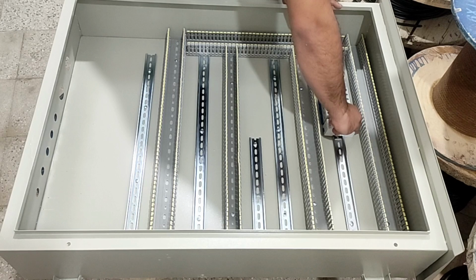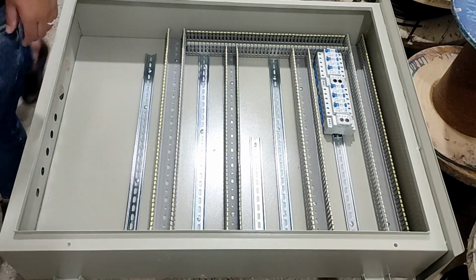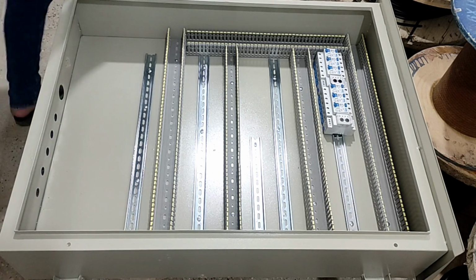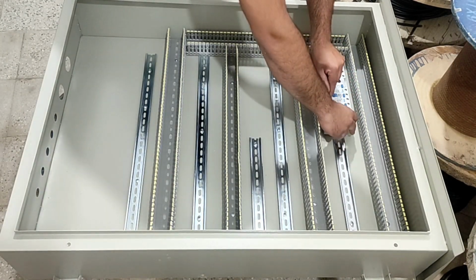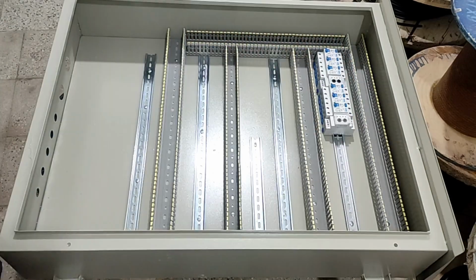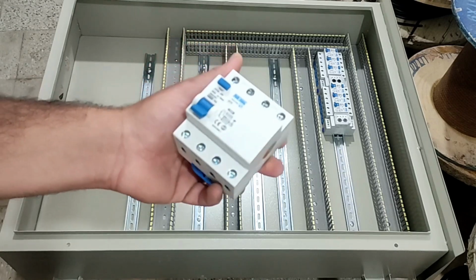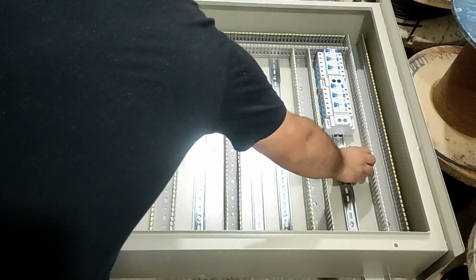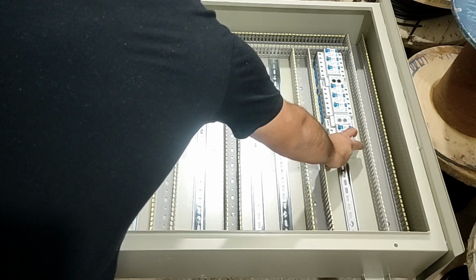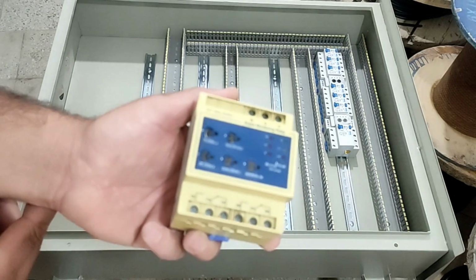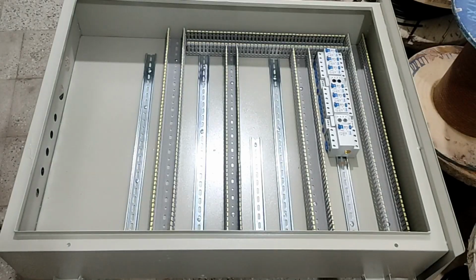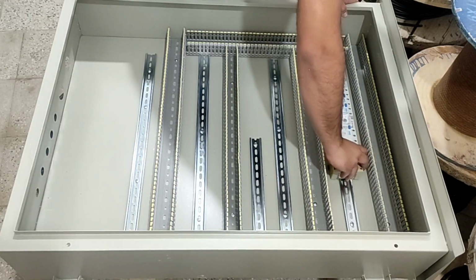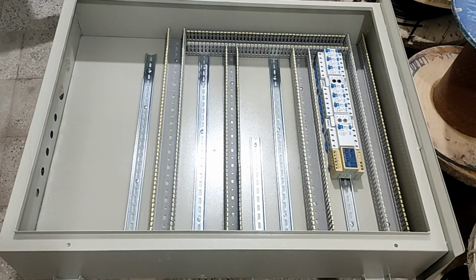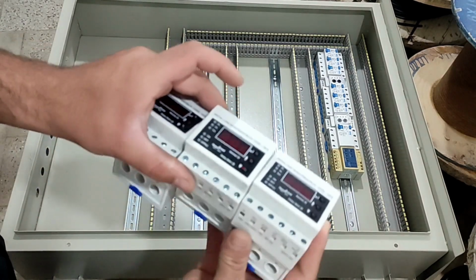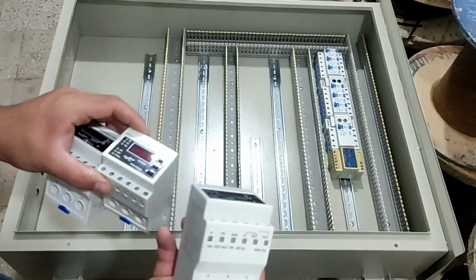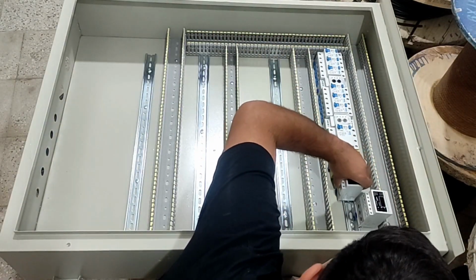And this is for the next 3 switches and the corresponding 3-phase monitoring relay. We install a 3-phase RCCB switch for 3-phase consumers. And along with it, we install a 3-phase monitoring relay to control the phases of this switch and protect 3-phase consumers from electrical damage. We also use 3 current controller relays that control the current of each phase and send a warning message if the current increases or decreases.